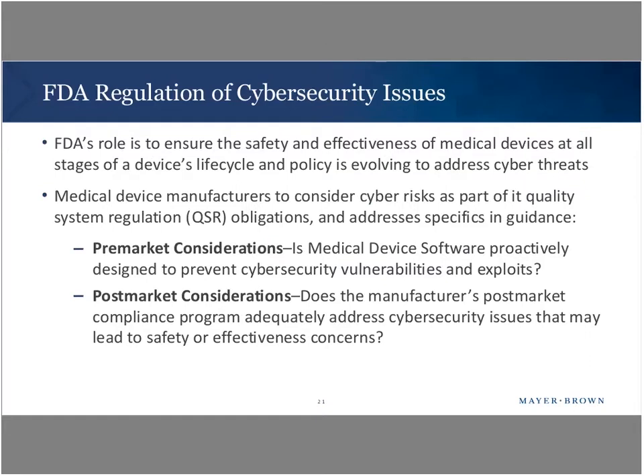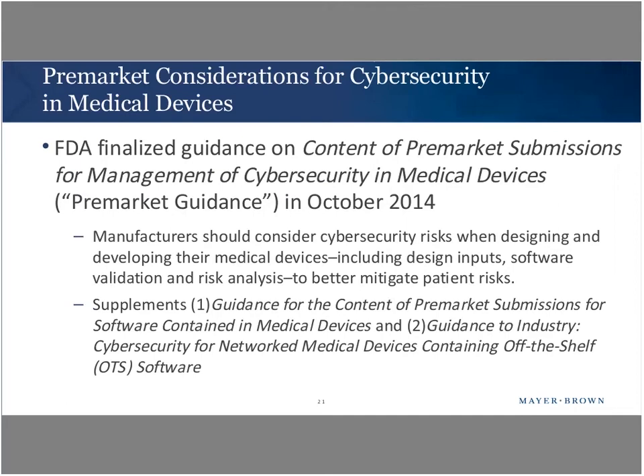So to get into the pre-market considerations a little bit, you have to look at the product when you're designing it to determine where there might be vulnerabilities, and how you can proactively address those vulnerabilities. This guidance document was meant to supplement two other guidance documents that relate to software, both off the shelf and software that is contained within, seeing as how software is essentially what provides the direct port for cyber attacks. So those three should be read together.